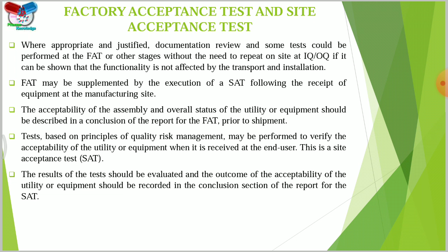So next stage of qualification is IQ, that is installation qualification. So the word also talks about installation. It means we are installing the equipment instrument at our site. So the basic definition of installation qualification is the documented verification that the facility, system and equipment as installed or modified comply with the approved design and manufacturer's recommendation. IQ should be performed on equipment, facility, utility, system and verification prior to installation of utility and equipment in an appropriate location.